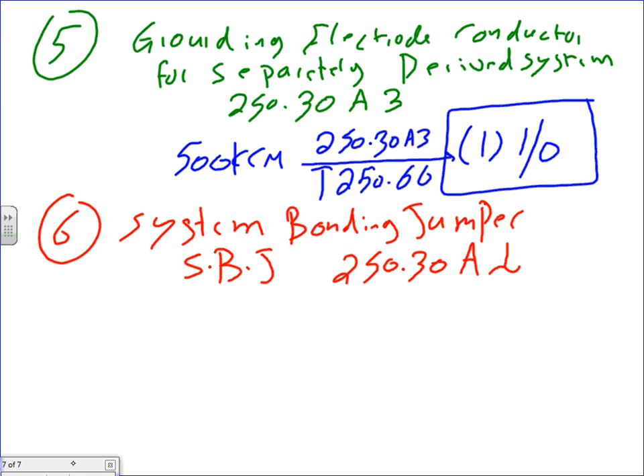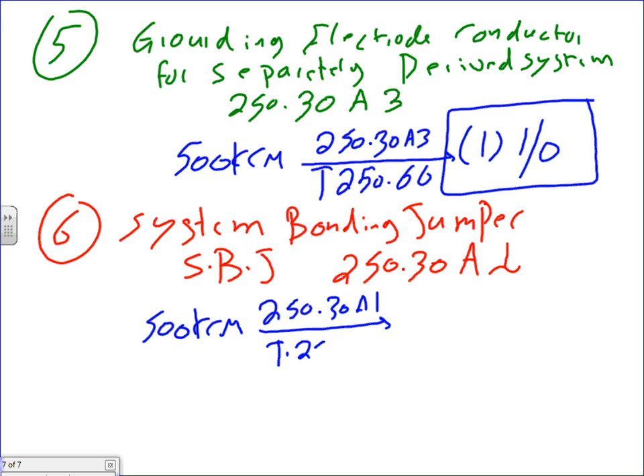If you go to 500 kcmil, 250.30(A)(1) refers you to Table 250.66. And it says that if it's higher than 1100 kcmil, you have to go 12.5% of the feeder.